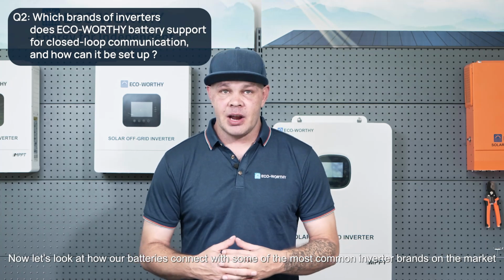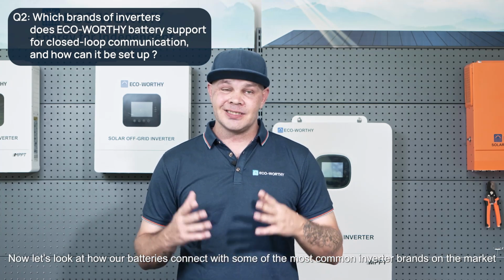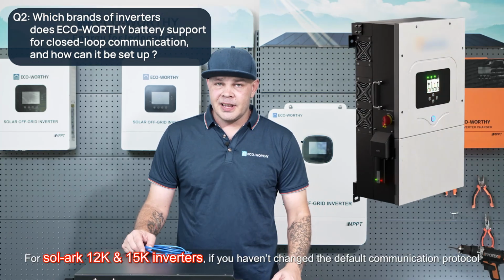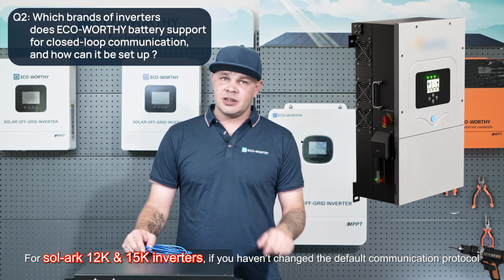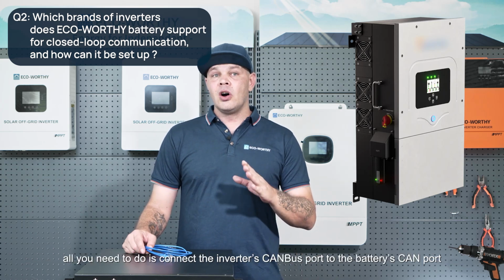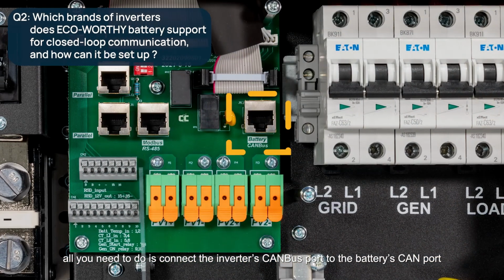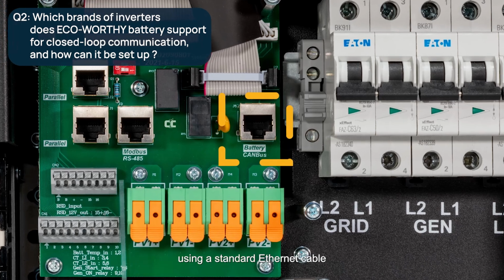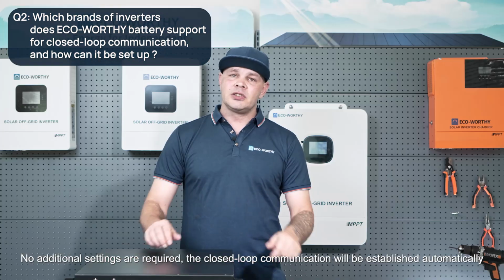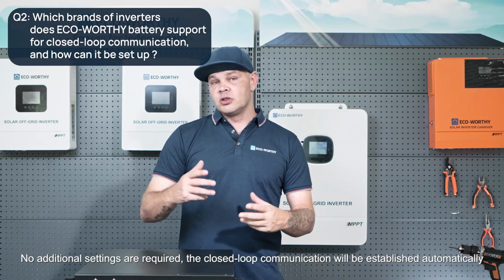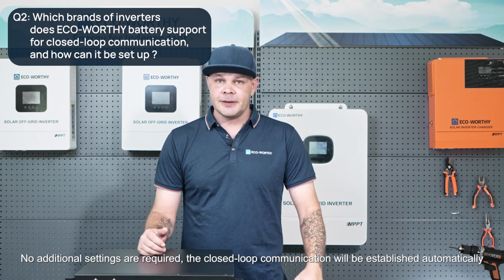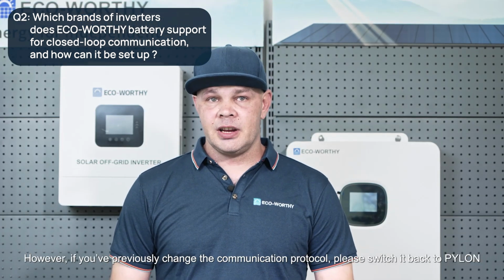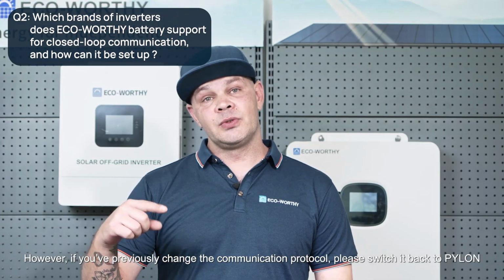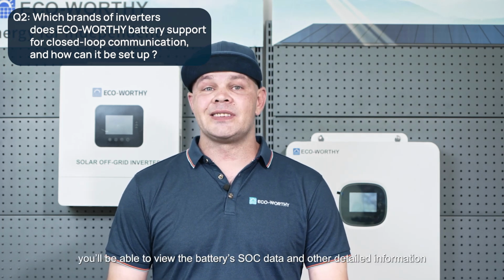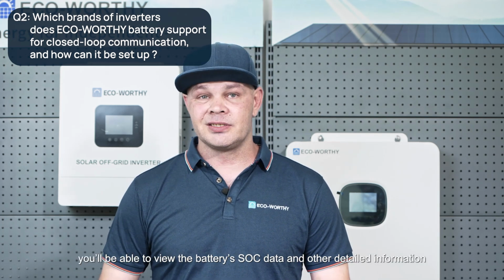Now let's look at how our batteries connect with some of the most common inverter brands on the market. For the SolArk 12K and 15K inverters, if you haven't changed the default communication protocol, all you need to do is connect the inverter's CAN bus port to the battery's CAN port using a standard Ethernet cable. No additional settings are required. The closed loop communication will be established automatically. However, if you've previously changed the communication protocol, please switch it back to Pylon. Once the communication is established, you'll be able to view the battery's SOC data and other detailed information directly on the inverter screen.